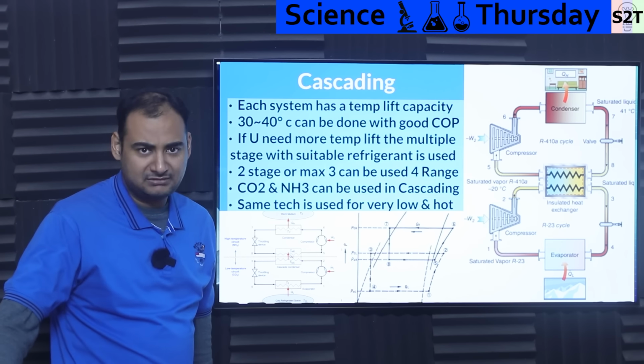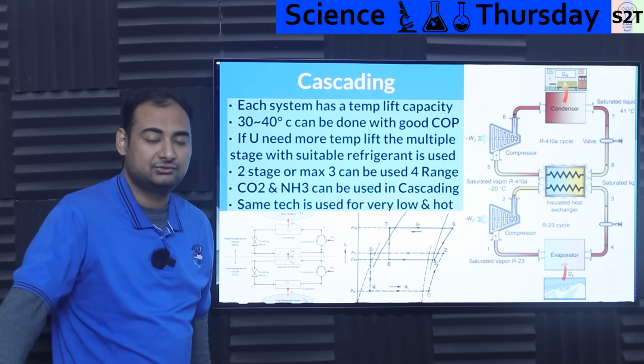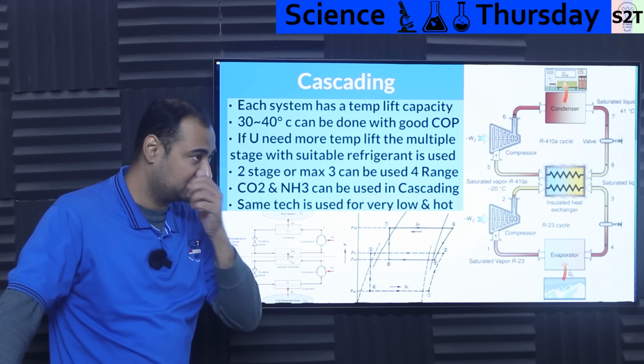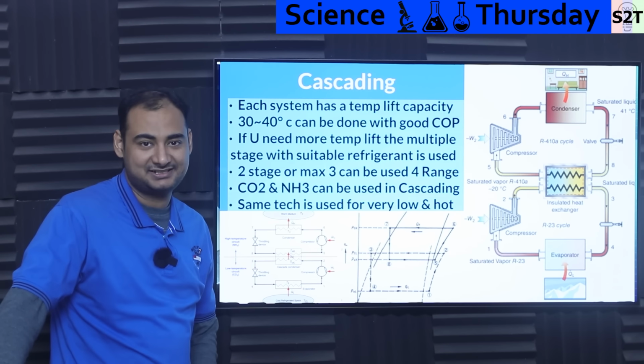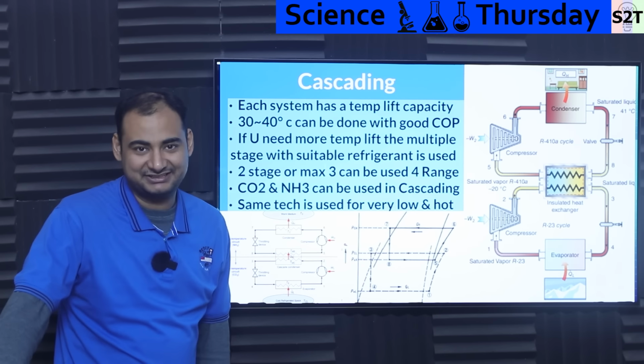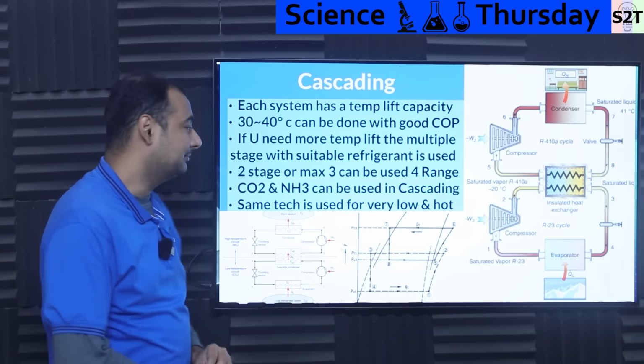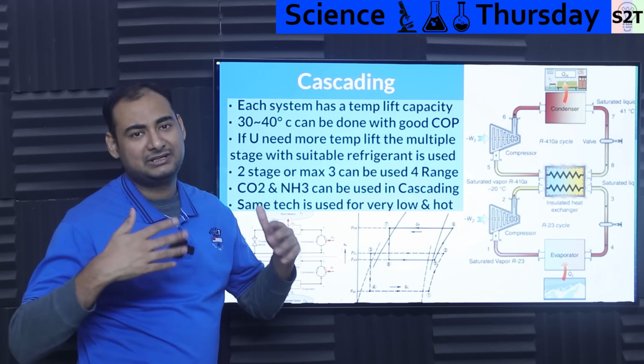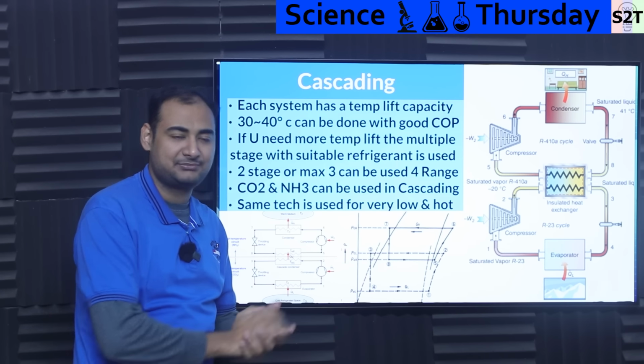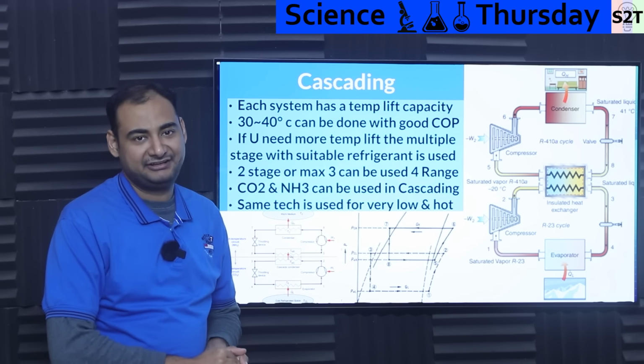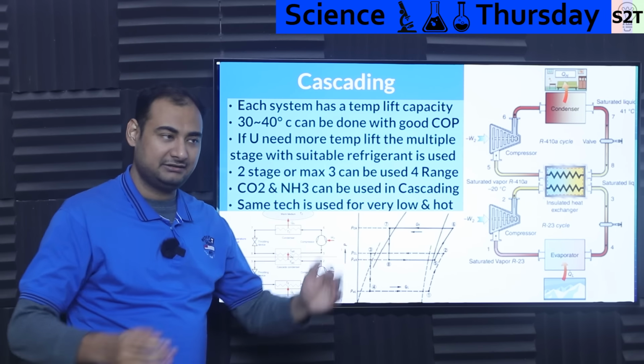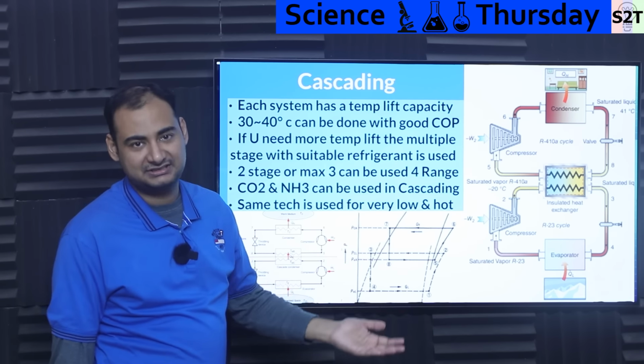Generally 2 is optimum, 3 you can do. Sometimes you require very low temperature, like let's say you want minus 150 degrees Celsius — yeah, you need 3 systems. 4 is also done, but the more you add, the more inefficient the system becomes, because yes, you will reach the temperature, but COP will drop to 0.5. So again, if you need that temperature, you need it at the end.